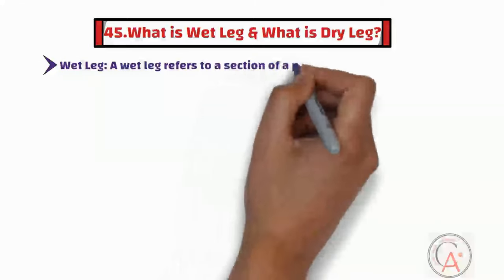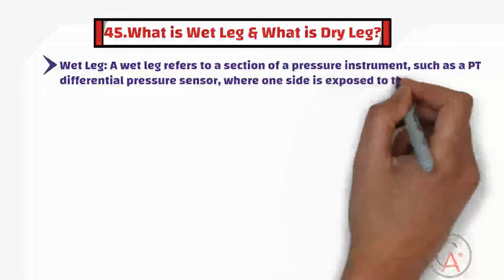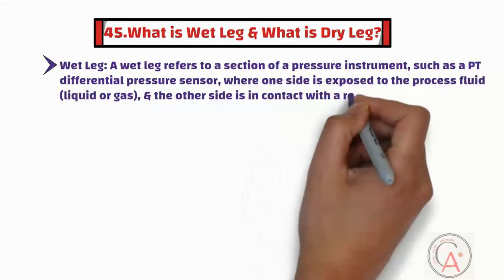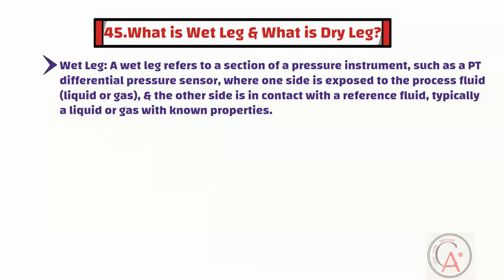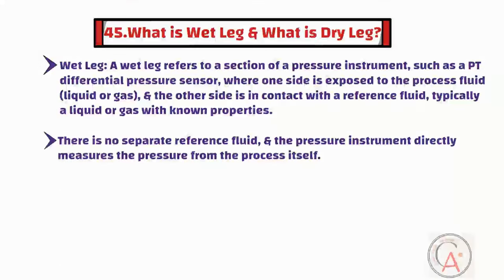Question forty-five is: what is a wet leg and what is a dry leg? A wet leg refers to a section of a pressure instrument, such as a pressure transmitter or differential pressure sensor, where one side is exposed to the process fluid and the other side is in contact with a reference fluid with known properties. In a dry leg setup, there is no separate reference fluid, and the pressure instrument directly measures the pressure from the process itself. Dry leg configurations are used in situations where it is not practical or necessary to use a separate reference fluid.